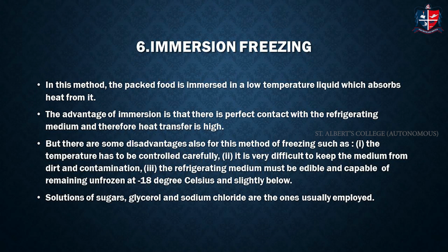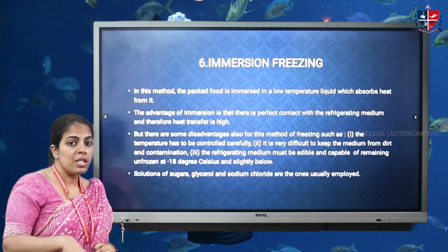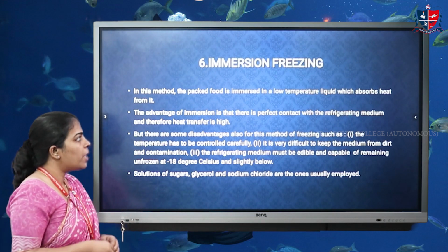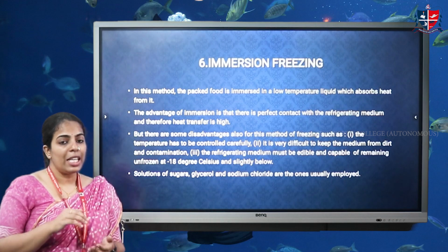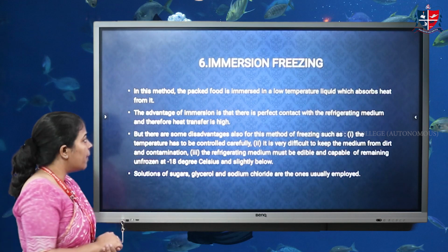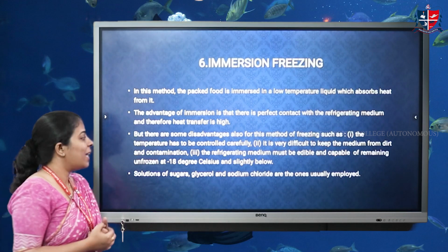Now, next is the immersion freezer. As from the name itself we can think what kind of freezer it is, where a product is immersed in a very low temperature liquid which absorbs the heat from it. The major advantage is that it has very close contact with the refrigeration medium. So because of that, the heat transfer is very high.